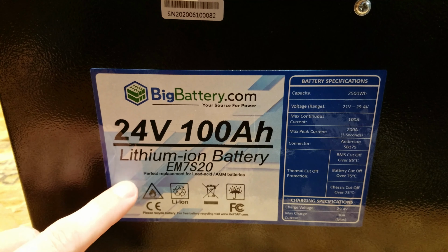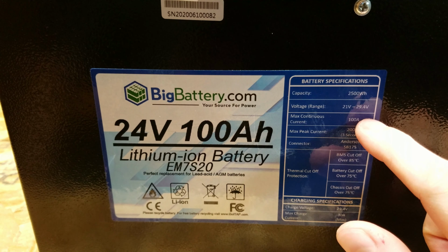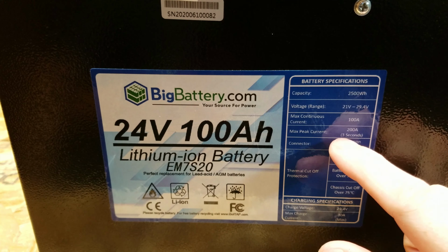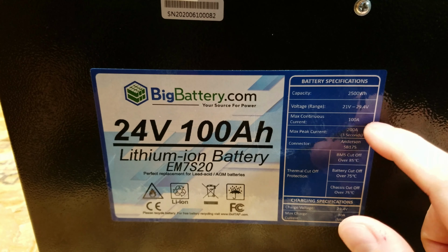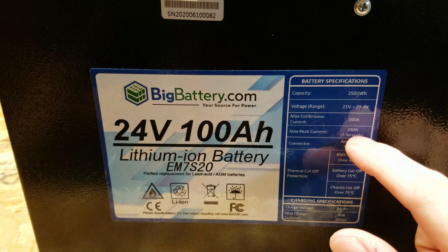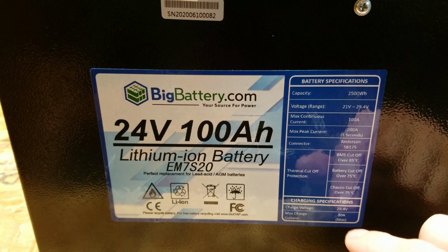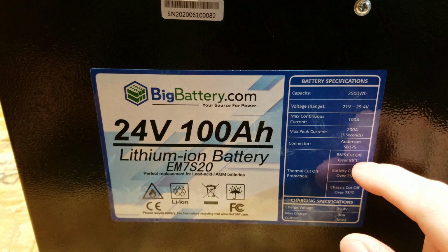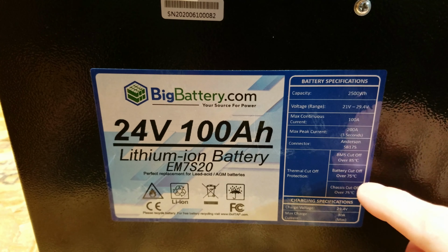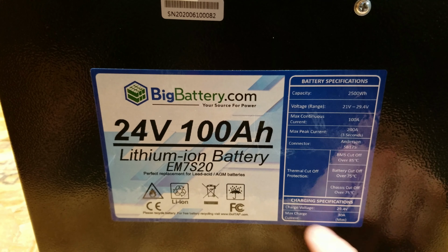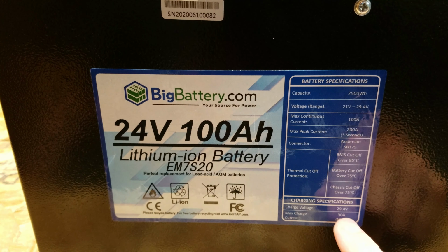You can see the specs here on the front: 2.5 kilowatt hour, minimum and maximum voltage. The max continuous current is 100 amps, and the max peak current is 200 amps for 3 seconds. There's a variety of BMS and thermal information here as well, and the max charging current is 30 amps, another important number to take note of.